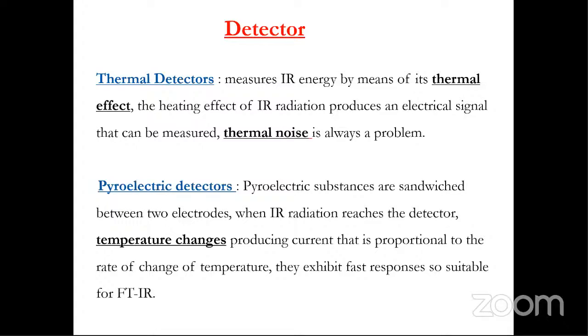Detectors. There are two types of detectors being used: thermal detectors and pyroelectric detectors. Thermal detectors are more or less obsolete now. They have a lot of thermal noise, so it creates an interference problem. So now we are using pyroelectric detectors, and they are used for FTIR systems. How do they work? IR radiation reaches the detector, and there is a temperature change producing a current that is proportional to the rate of change in temperature, and we get the FTIR response.